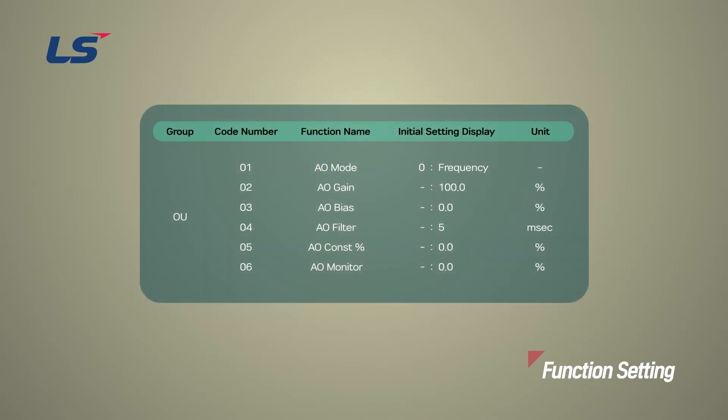In OU group 2, you can set the gain value for analog output. And in OU group 3, you can set the bias value for analog output. Gain and bias are reflected in the output as the formulas shown on the screen.